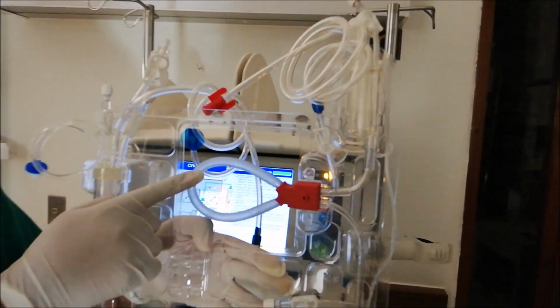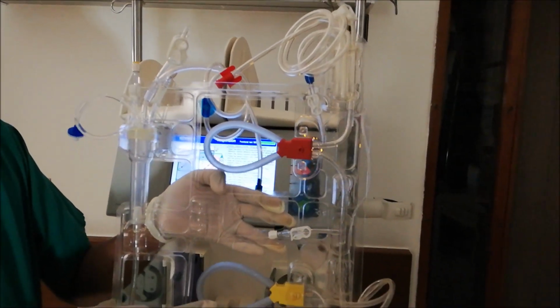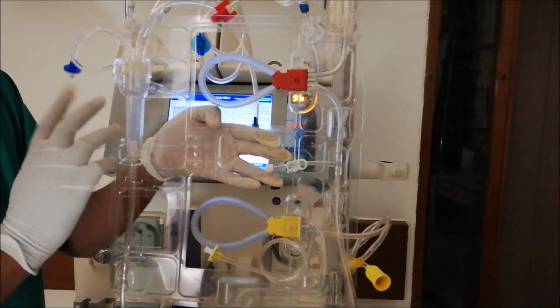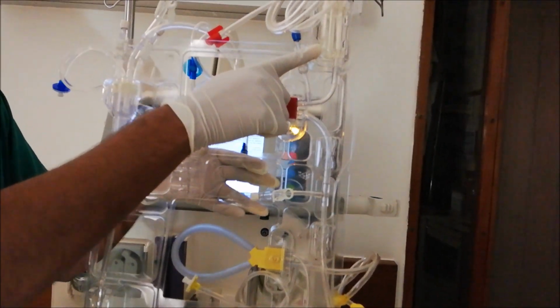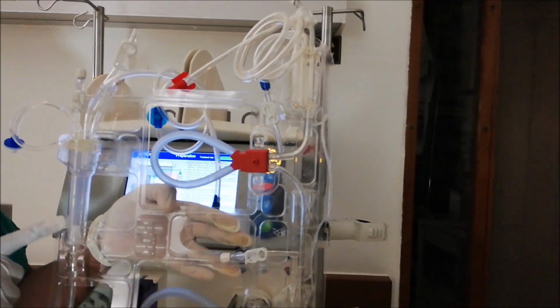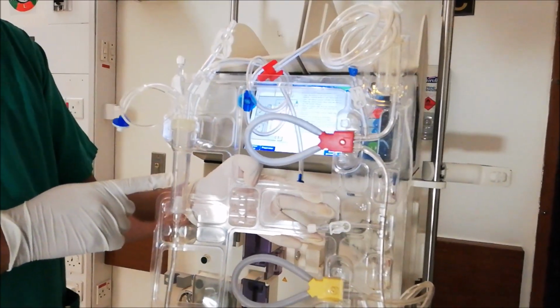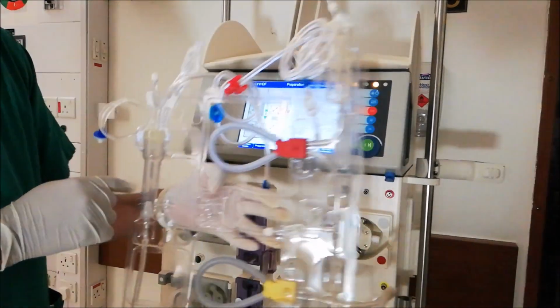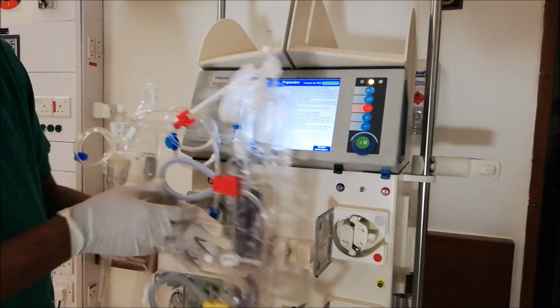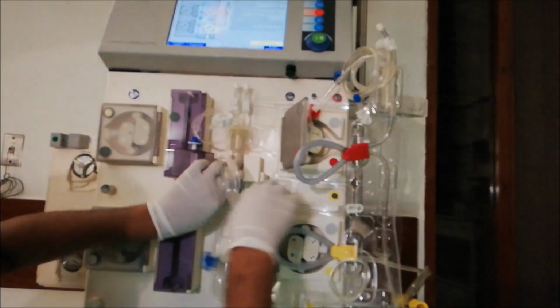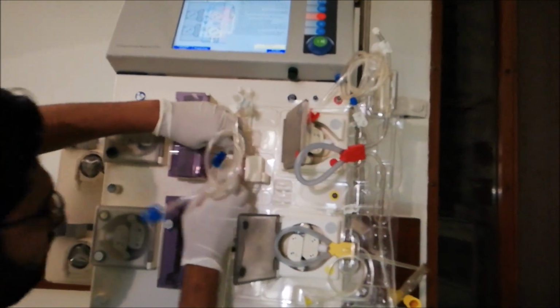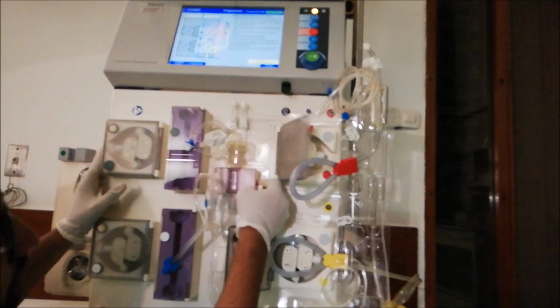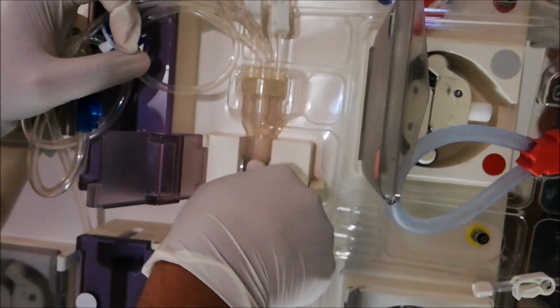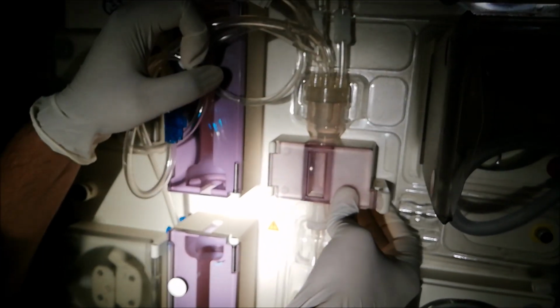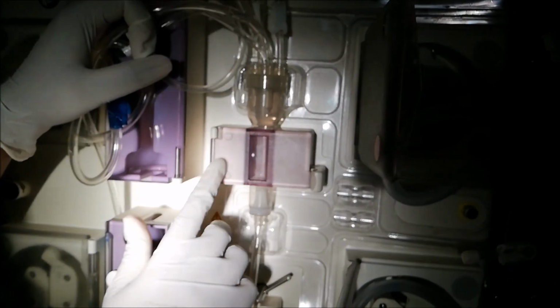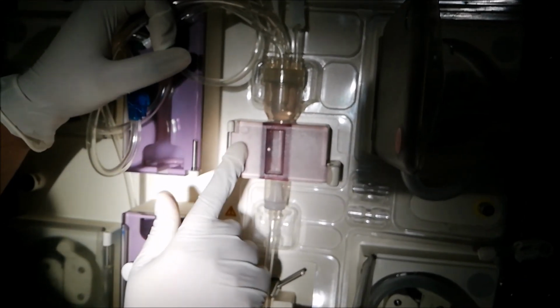Red tubing is for blood pump. Yellow tubing is for filtrate pump. It also has 2 chambers. It is arterial chamber and this is venous chamber. Now we have a venous bubble catcher to insert in air leak detector, and fix the venous bubble catcher into air leak detector and close the window. Now venous bubble catcher is inserted in air leak detector.